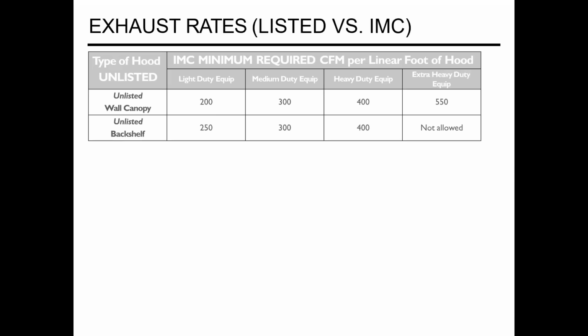So as we were talking about IMC, this is the minimum CFM requirements for an unlisted wall canopy, unlisted back shelf hood, depending on the cooking rating. So your light duty, medium, heavy, and then extra heavy duty would be your solid fuel, which is starting to be a little bit more prevalent in a lot of open kitchen designs.